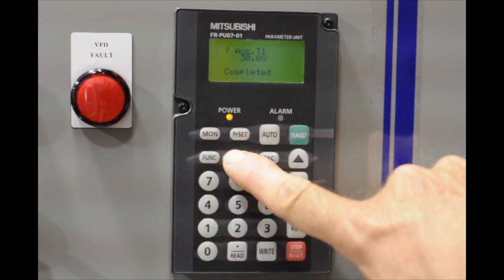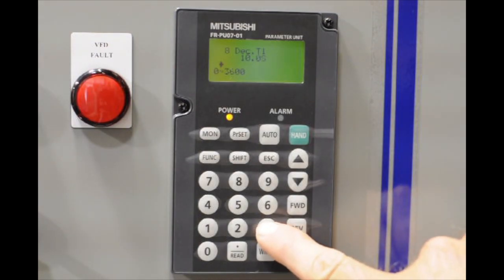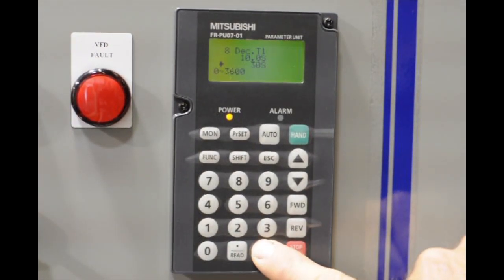Again, it blinks. We're going to move on to parameter eight, which is the decel time, and this one is set up for 10 seconds, and we're going to go ahead and put in 30 also. Three zero, and hit write.